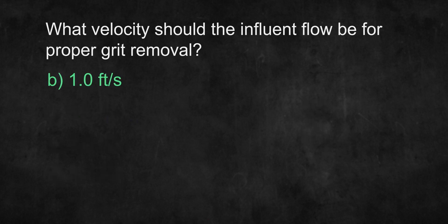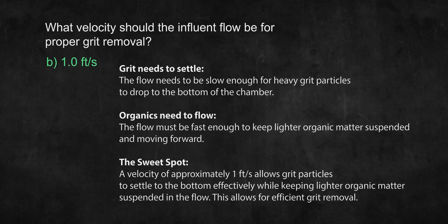The answer is B: 1 foot per second. Grit consists of heavier materials like sand, small stones, and other dense debris. To remove these, we need to strike a balance with the flow of the influent wastewater. If the velocity is too low, organic matter will start settling along with the grit, which is undesirable. On the other hand, if the velocity is too high, it will start scouring the already settled grit and carry it away, causing issues with downstream equipment and processes. A flow rate of around 1 foot per second creates ideal conditions, allowing grit to settle efficiently while keeping lighter organic matter suspended for proper separation during wastewater treatment.